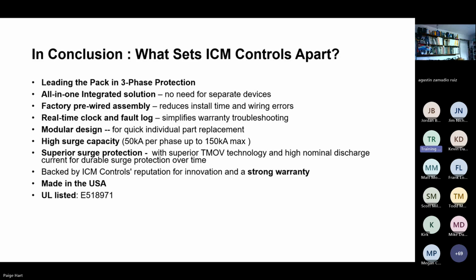The real-time clock and fault log memory in the 450A Plus is a real good bonus. One of the things that almost everybody I talk to that wants three-phase voltage monitoring loves is the idea of having a date and timestamp on the fault so they can do more diagnostics. So this is great for diagnostics and simplifies troubleshooting when somebody has to call in for a warranty or anything, even if they're just going out for a service call. The modular design is great for quick individual part replacements. The high surge capacity of 150,000 amps for a single event and 50,000 amps per phase is great.